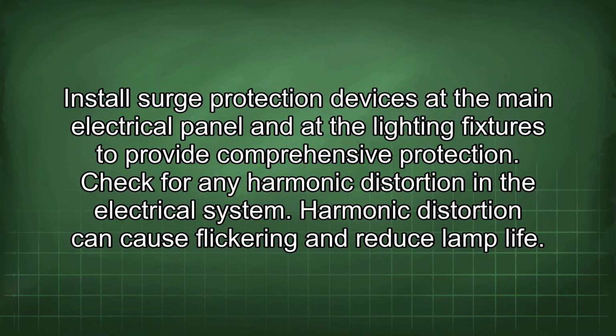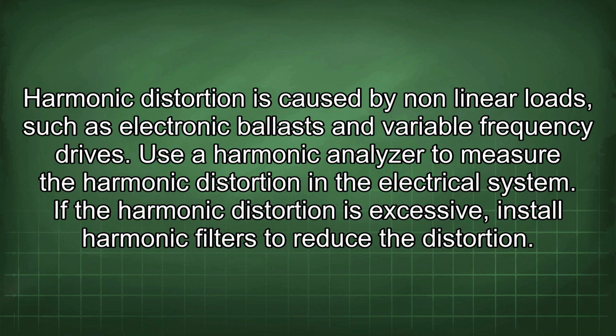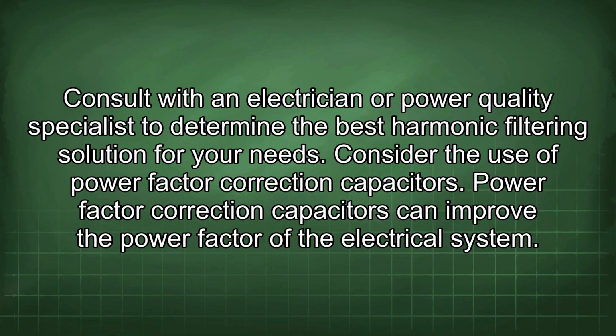Check for any harmonic distortion in the electrical system. Harmonic distortion can cause flickering and reduce lamp life. Harmonic distortion is caused by nonlinear loads such as electronic ballasts and variable frequency drives. Use a harmonic analyzer to measure the harmonic distortion in the electrical system. If the harmonic distortion is excessive, install harmonic filters to reduce the distortion. Consult with an electrician or power quality specialist to determine the best harmonic filtering solution for your needs.